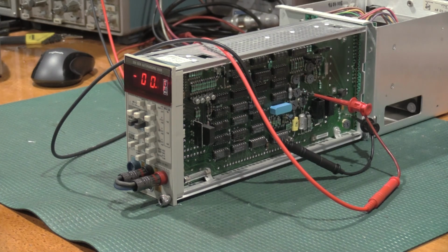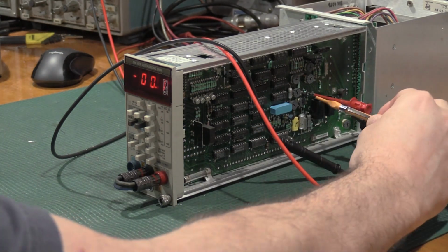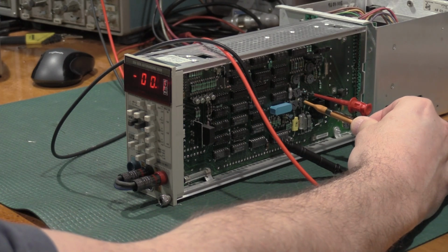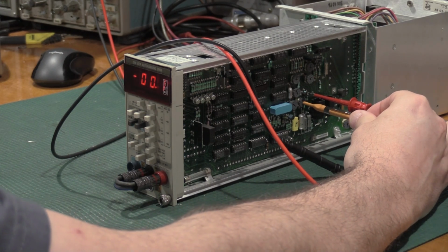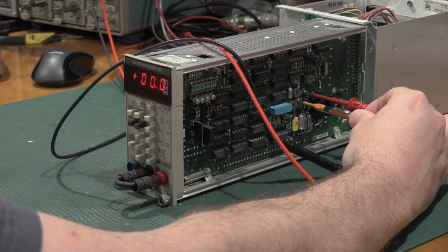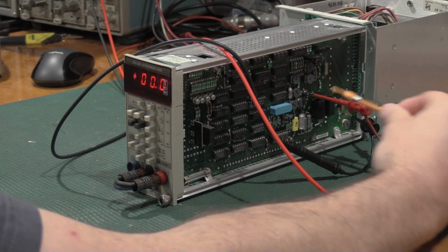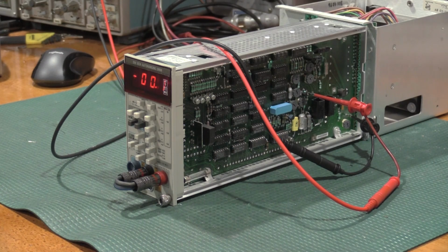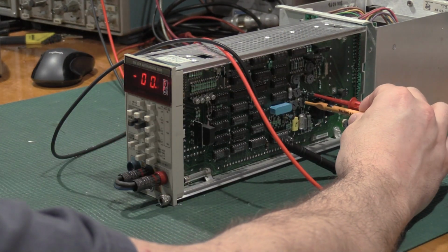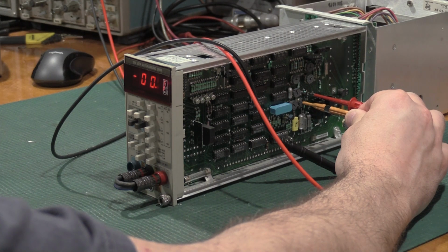Well, it was doing this before, but we are going to need to adjust the DC 0, which is right here. It's actually not a bad angle for you guys to see what I'm doing. There we go. So it does need to be adjusted a little bit. We do have a nice shorting bar on the front. And everything is good. We're going to need to press into using the Fluke next for the voltage calibrators. Actually, that's not holding 0 very well. That should probably move a little bit more.